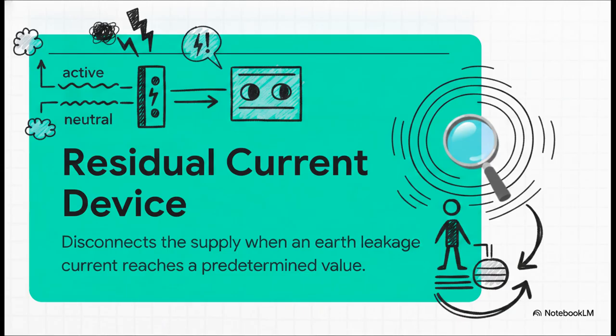That is why the rules heavily mandate the RCD, or residual current device. Let's cut through the jargon for a second. An RCD is essentially the ultimate reflex system of your fortress. It constantly monitors the current going out on the active wire and coming back on the neutral wire. If it senses that power is leaking out of the system, meaning less is coming back than what went out, it assumes that current might be leaking through a person into the earth.